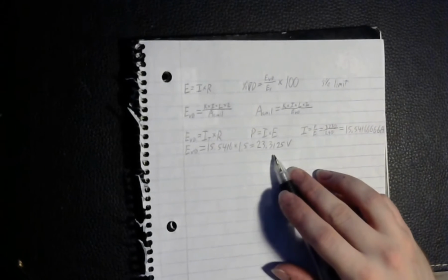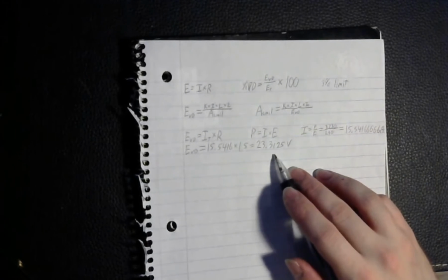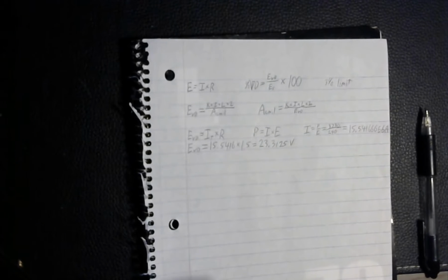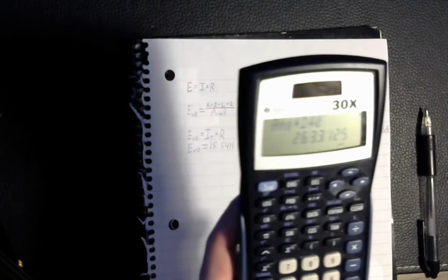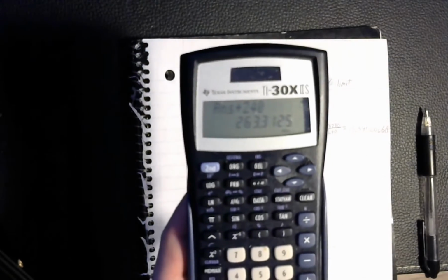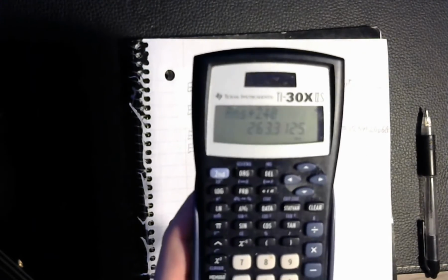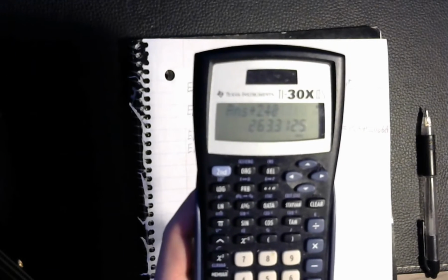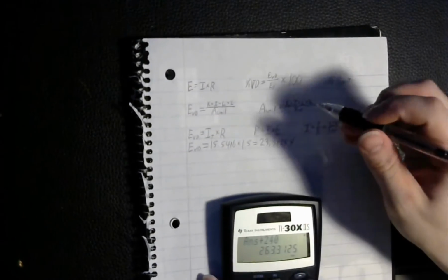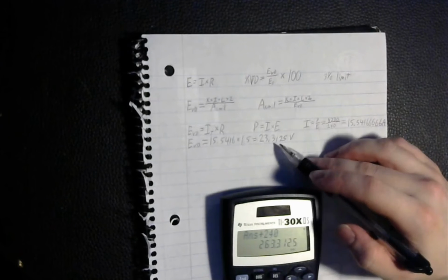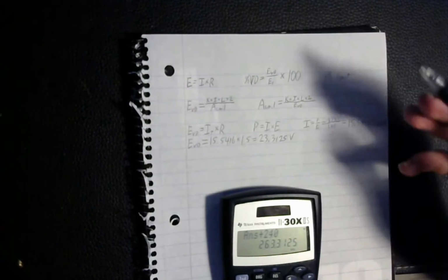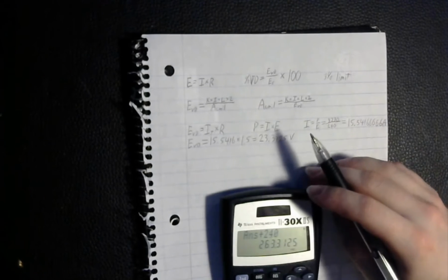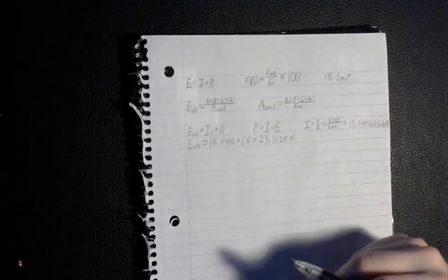We know we want 240, so we literally just add 240 to that, and our answer. I don't know why that looks backwards on my camera. That does look forward to you, right, on your view? I couldn't get the video to see, so it's okay. I'm listening. But once you add this voltage drop to your desired voltage at the load, you should end up with about 263 volts.